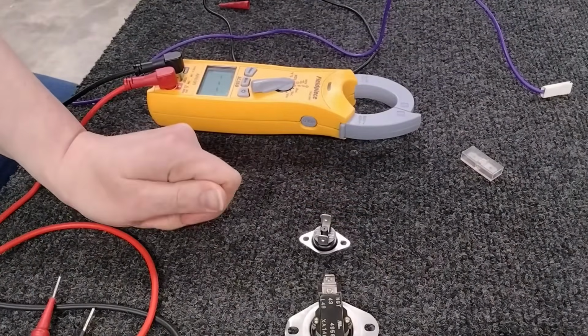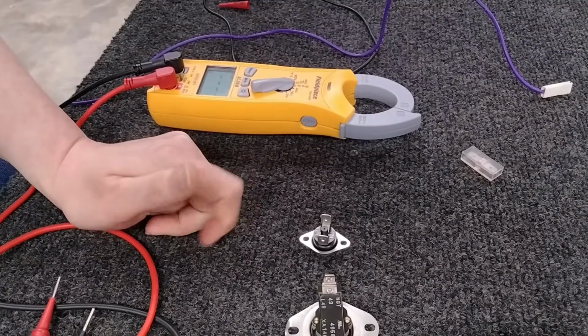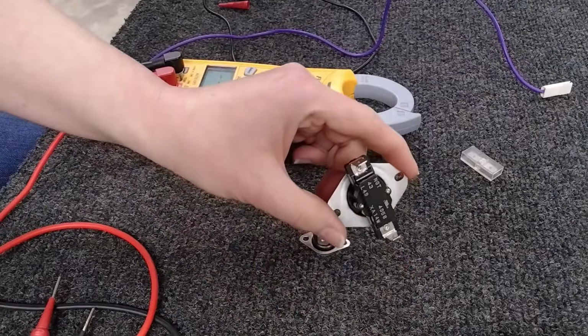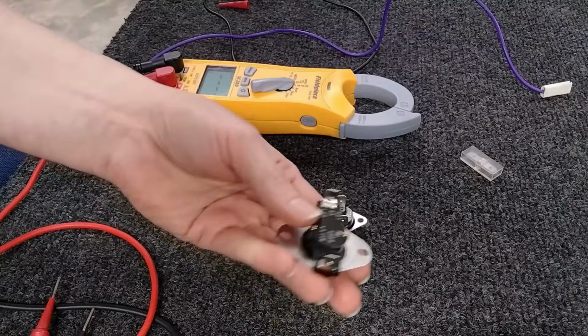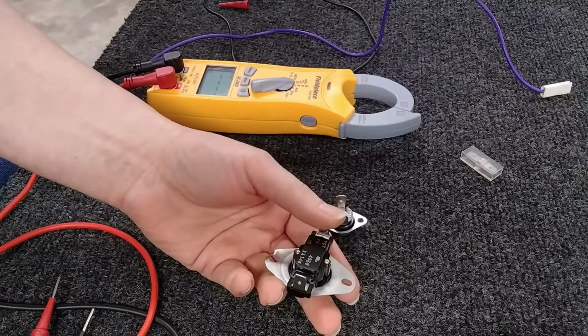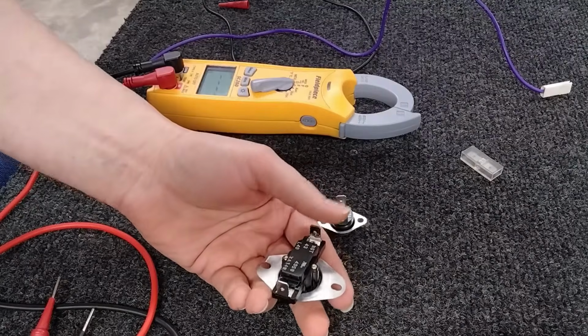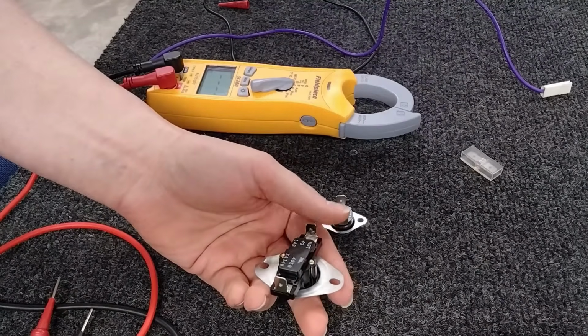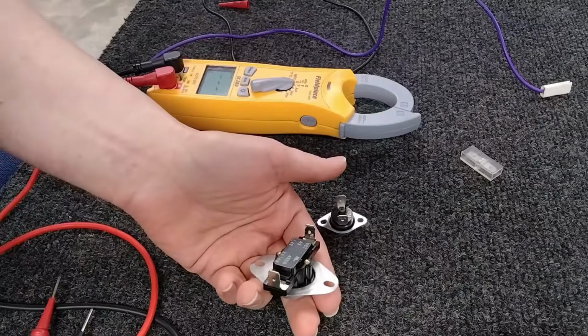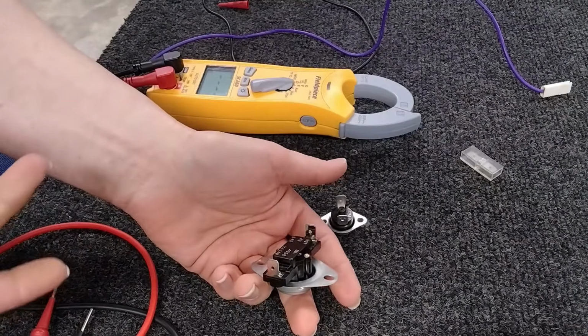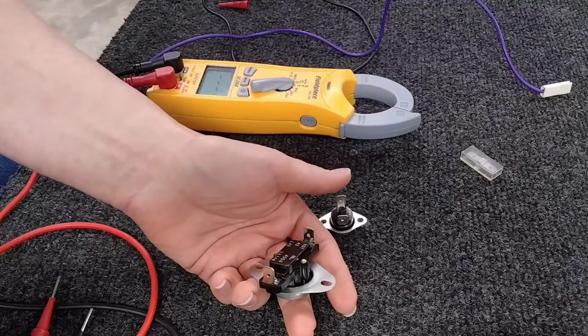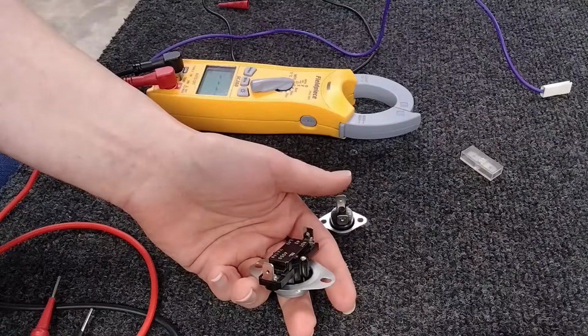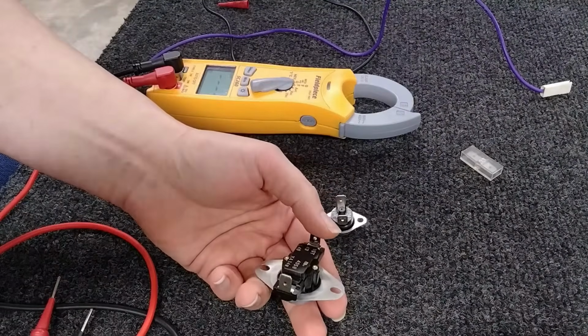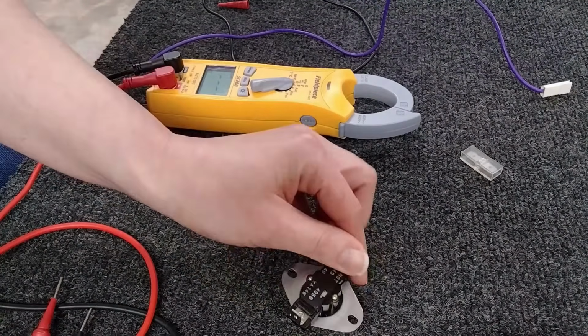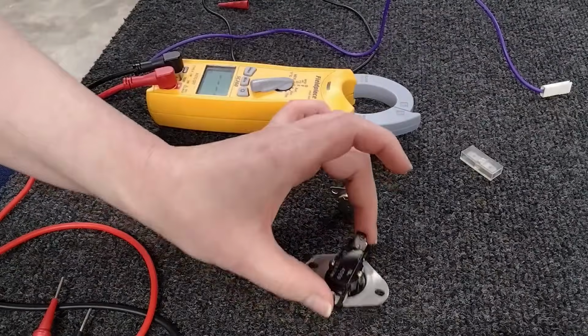Testing limit switches can be frustrating at times because sometimes they can test good, and then the same problem happens where your furnace cuts off after it stays on for, say, a couple hours, or maybe you're having some sort of intermittent functionality where it'll come on for a few days or a week, and then all of a sudden it does it again, where it causes the machine to cut off. So there's other ways to test around that.